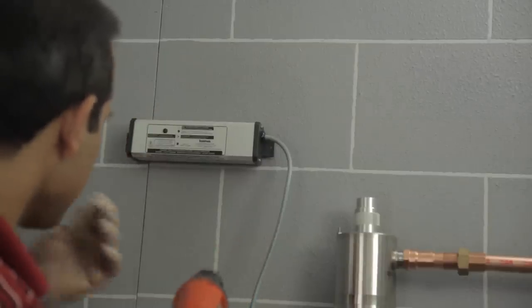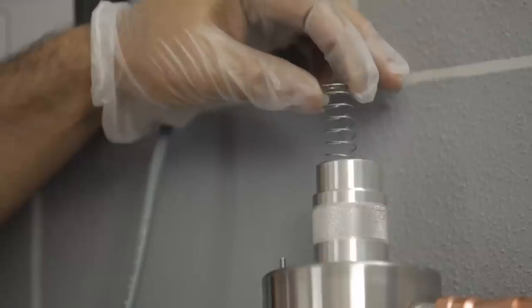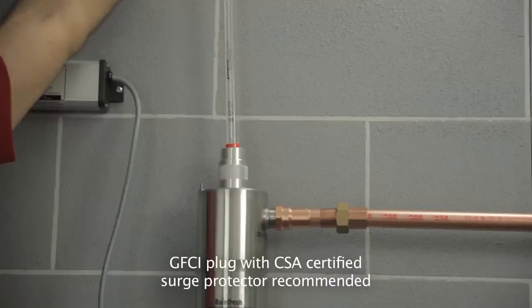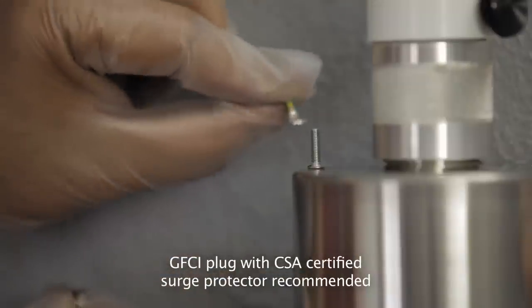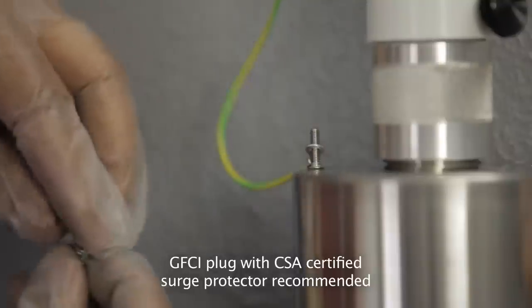Mount the electronic ballast on the wall using the screws included. Drop the lamp spring inside the dome. Hold and slide the lamp into the dome and connect it to the ballast. Connect the green grounding wire to the grounding stud and tighten the nut.